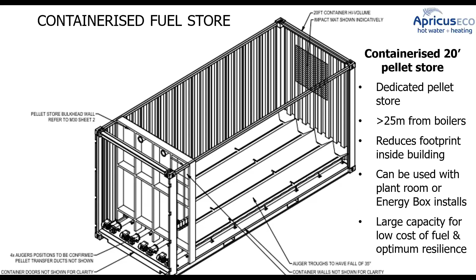If there is a bit more load and there's space for a container, then this can be combined just as well with a plant room install. Because we can go 25 meters from the boilers, those vacuum hoses that we saw that go into the top of the boiler can transfer the fuel from this to the boiler inside the building. So you've got some penetration through the wall, but they can be easily flashed, and detailing under E2. They don't pose a fire risk particularly because pellets won't ignite in the same way that gas or fuel will, and there can be auto closing wall penetration kits as well, so it locks it closed if there's a fire. And you get a really good capacity of fuel storage, meaning that you get good resilience and low cost of fuel. So these hybrid systems, they're important when we look at how we detail the actual application of renewables going forward.